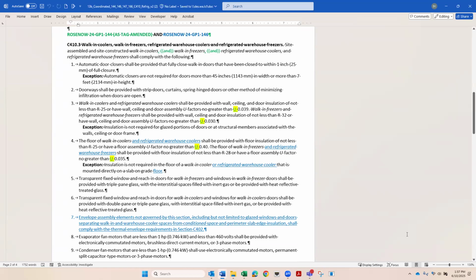Under 146, item number 4 adds that the floor of walk-in coolers and refrigerated warehouse coolers has to meet the U-factor or R-value requirements. Before, it just said walk-in coolers. There's still an exception for a walk-in cooler or refrigerated warehouse cooler mounted directly on a slab-on-grade floor, so that's just clarifying that exception.